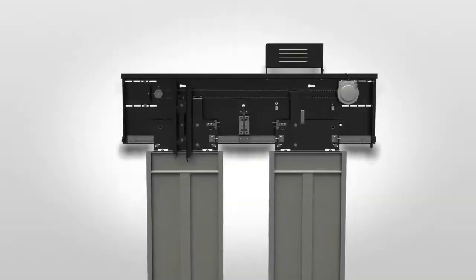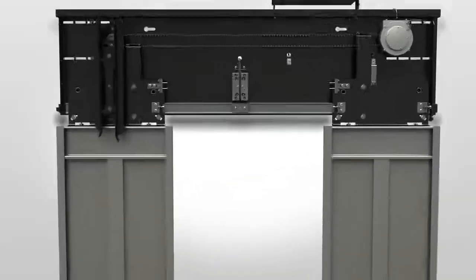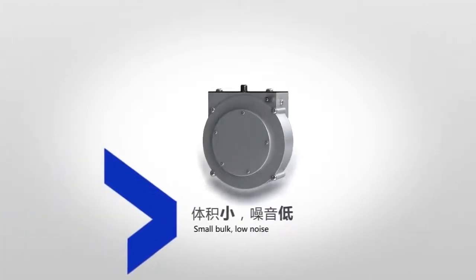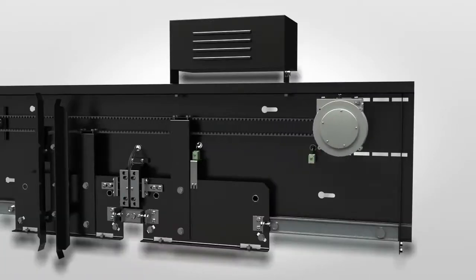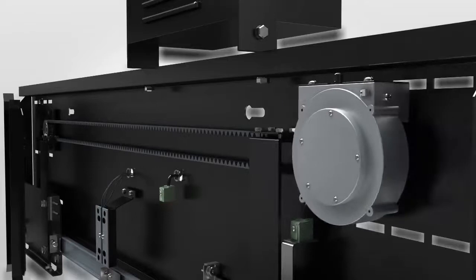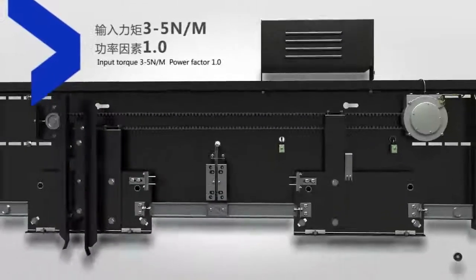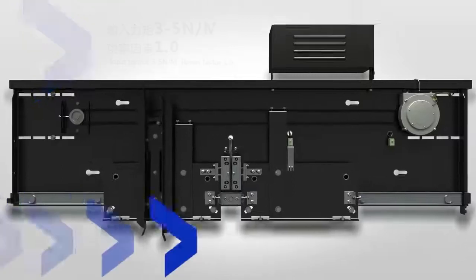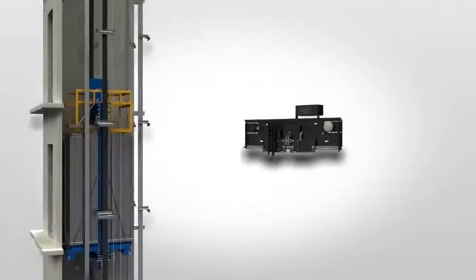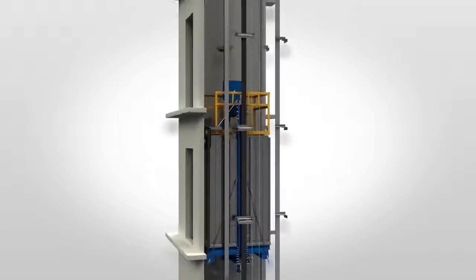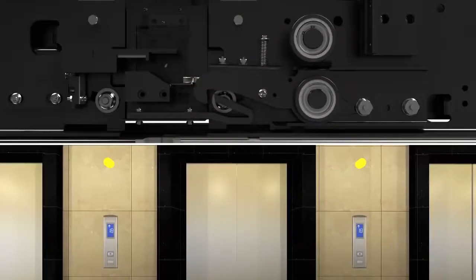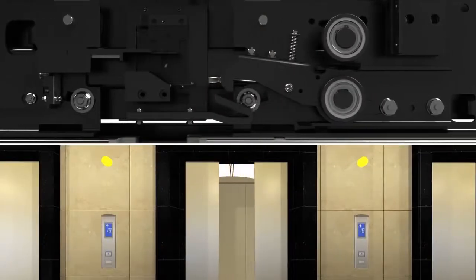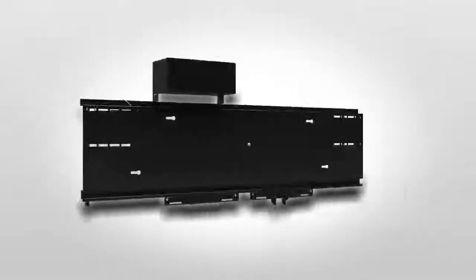Under permanent magnet synchronous motor drive, it ensures proper door opening and closing. Torque transfers via motor synchronous belt direct drag, providing constant torque. The door operator is compact in structure and strong in overloading, maintaining smooth, effective running within 20% to 120% of the rated loading zone.